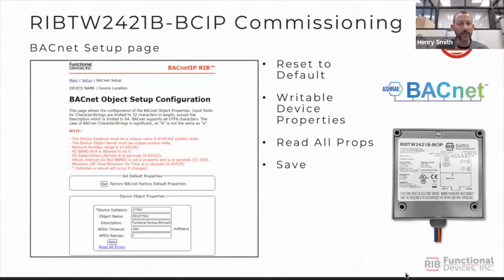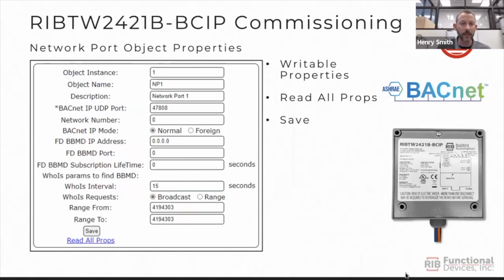And the last web page that would be available is the BACnet setup. Here are the device object properties. Any of the properties that are writable will have a text box available on the web page where you can write to those properties. And then again, you would need to save them on the web page. The little link below the save button is the read all properties, so that would give you a full list of all the readable and writable properties, not just the ones that you can write to. Here's just a snap of the network port object on the web page.